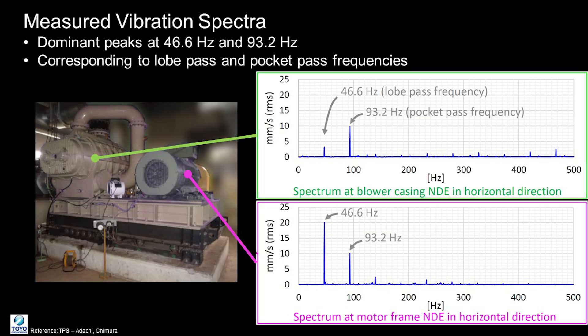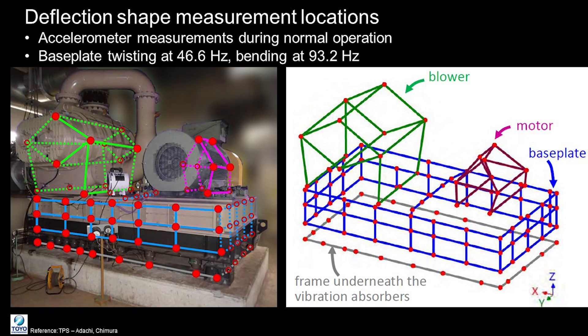Vibration measurements revealed dominant peaks at both 46 Hz and 93 Hz across the equipment. These peaks corresponded directly to the lobe pass and pocket pass frequencies, indicating that these were likely contributors to the system's vibration issues.